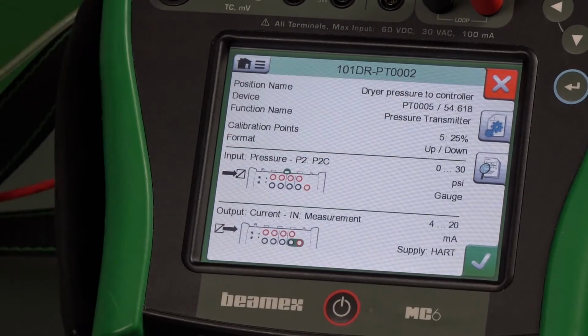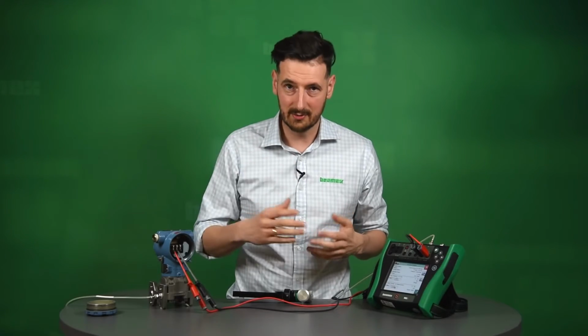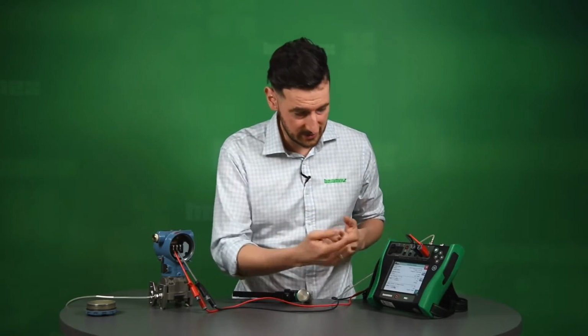That's why we've got 5 calibration points. We're going to go up and down. We're going to pressurize 0 to 30 psi and then back down. So that's what we're going to do.